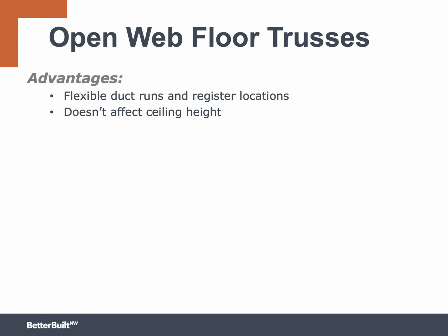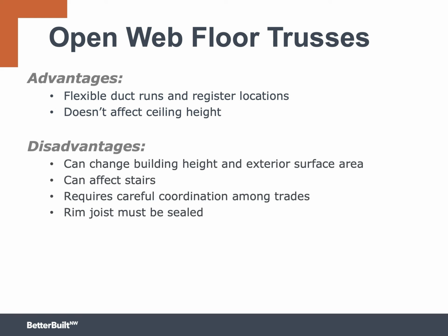The advantage of the open web floor truss strategy is that it's flexible. You can put duct runs and registers virtually anywhere on the first or second floors. It doesn't affect ceiling height. The disadvantages are that it can affect the overall height of the building and the amount of exterior surface material needed. It can also affect the stair configuration. You may need to add an additional riser. It does require careful communication between the trades because you're really putting a lot of stuff in that floor cavity. And don't forget the rim joists must be sealed.